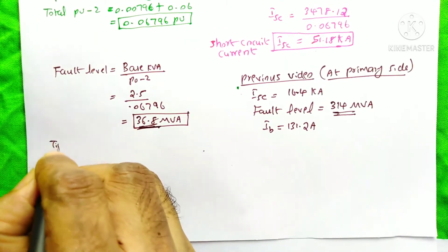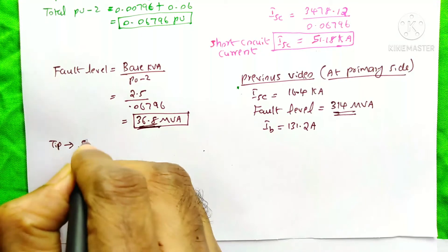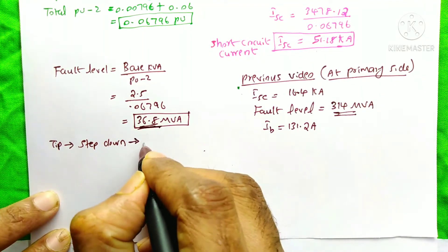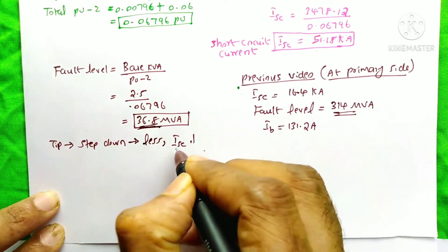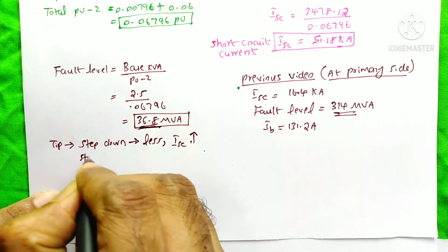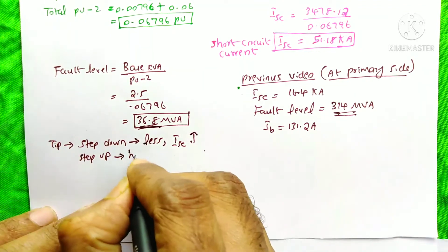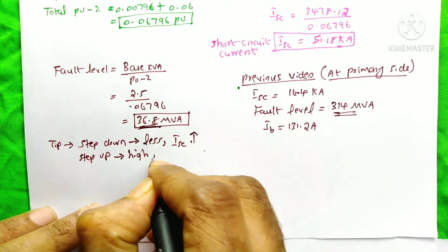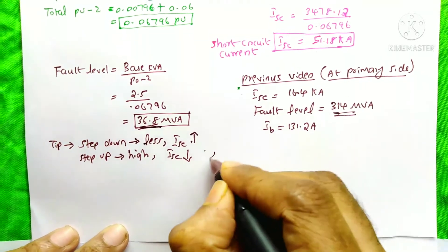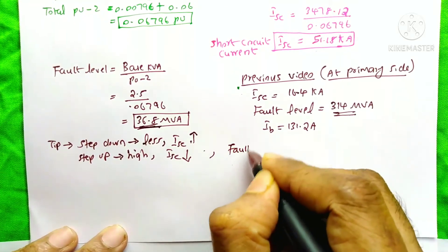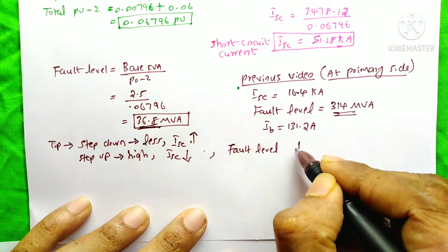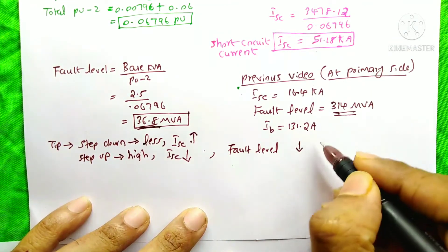Here is a tip: whenever our transformer is a step-down transformer, the voltage at the secondary side is less. Due to that, the short circuit current ISC will always be more. And for a step-up transformer, the voltage is high on the secondary side, so the short circuit current ISC is less. But when talking about fault level at the transformer, for any transformer, the fault level at the secondary side will decrease due to the increase of per unit impedance.